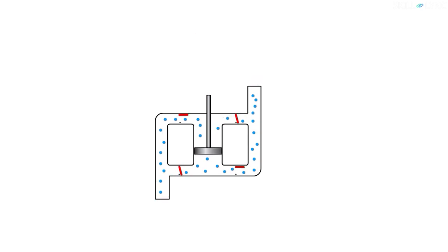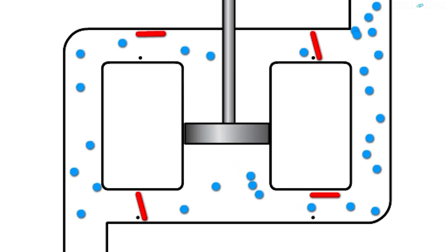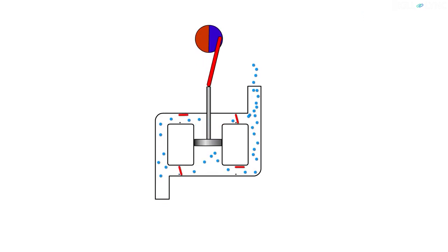This diagram explains the construction of the pump much better. As they say, a picture is worth a thousand words. As you can see, the pump has four valves instead of two. The output of the pump is doubled by utilizing the return stroke of the piston. When suction stroke occurs in one side of the piston, delivery stroke occurs on the other side. So, for one complete revolution of the crank, we will have two delivery strokes.